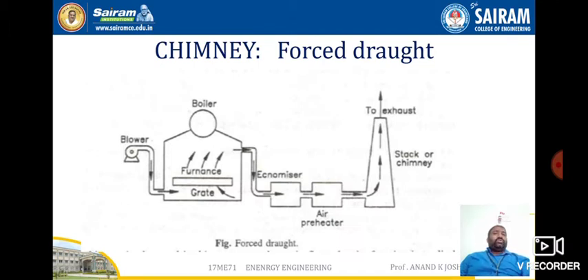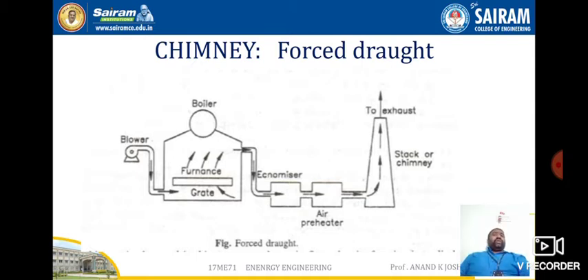Let us discuss about the chimney. A chimney is a system through which exhaust gas or flue gas is taken out to the atmosphere. In a forced draft system, a blower is installed near the base of the boiler and air is forced through the furnace. The flue economizer, air preheater, and stack are provided. This draft system is also called a positive draft system because the air pressure throughout the system is above atmospheric pressure.